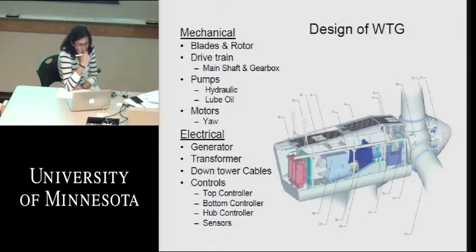The bottom controller is important because we don't normally have personnel in the wind turbine while it's operating. You don't want people up there at 300 feet off the ground with all the kind of forces shaking that big box up there. So they can fully operate the wind turbine from the bottom of the tower, where we have this bottom controller located. And it fully emulates all the functionality that the top controller uses and provides redundancy for the top controller.